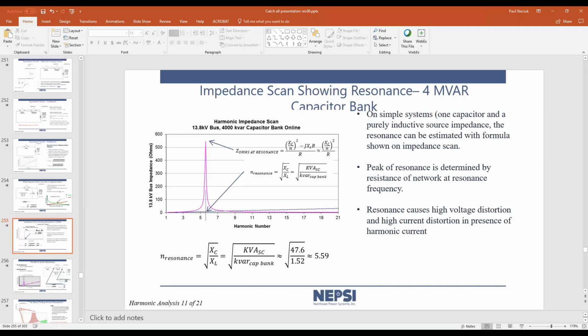On the y-axis you can have ohms, and on the x-axis you can have harmonic number, and each point on those curves represents the resulting voltage for 1 amp of current injection, which is interesting, because if you have a device that puts out 5 amps, then the resulting voltage is 5 times that value. And in this case, it would be nearly 2,500 volts for just 5 amps of current injection. So you can see where resonance is an issue here. So this is one of the key ways of interpreting the impedance scan.